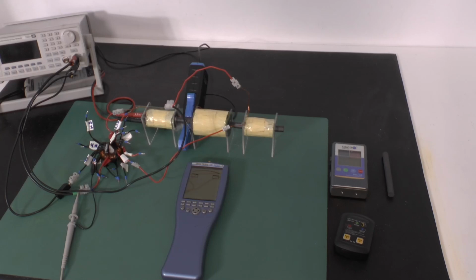On the right hand side you see 2 static meters. One simply shows polarity, and the small black one shows red and blue for either negative or positive, and also registers energy fluctuation from 50 Hertz. So we definitely have 50 Hertz from the room in the coils, but at a very low margin, which this one can measure. The more expensive one, which can go up to 20 kilovolts, will show that in much more detail, confirming we have technically almost no voltage, so there is no electrostatic voltage there.